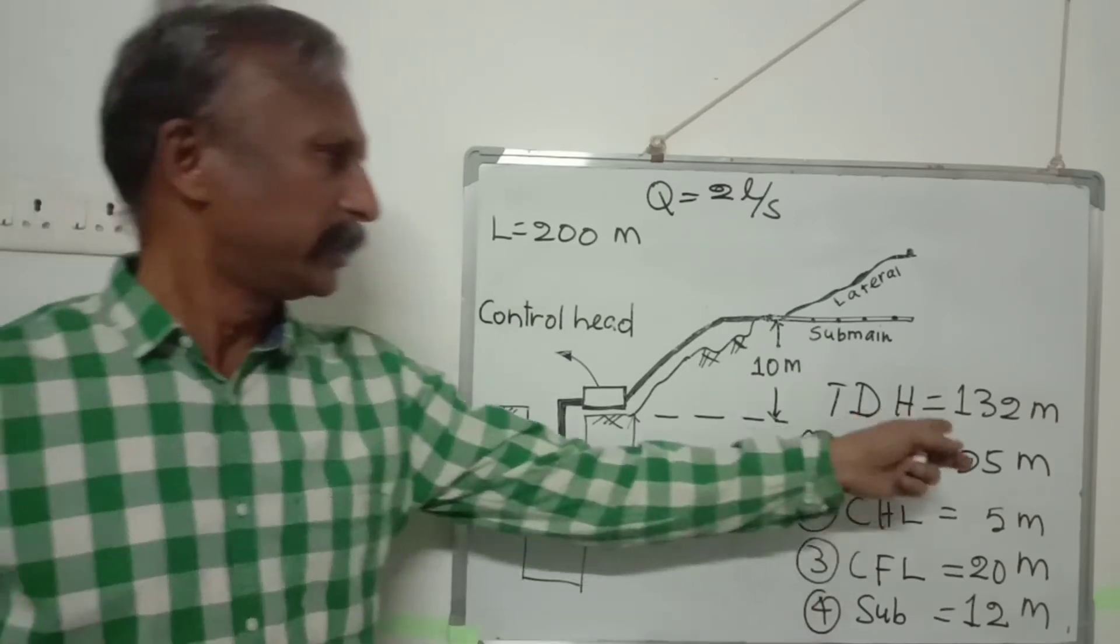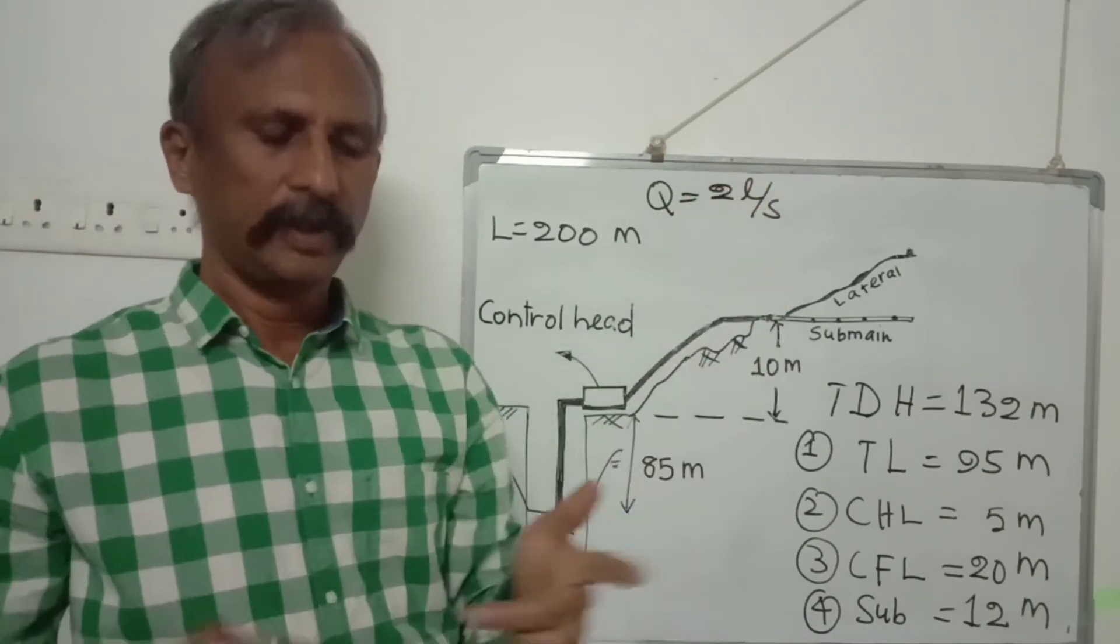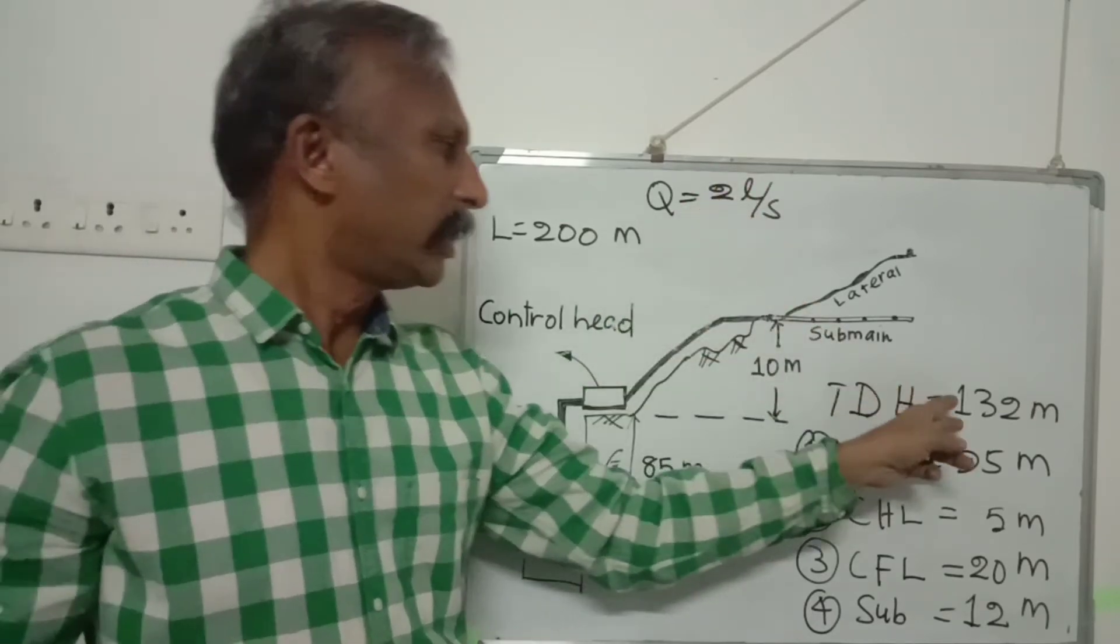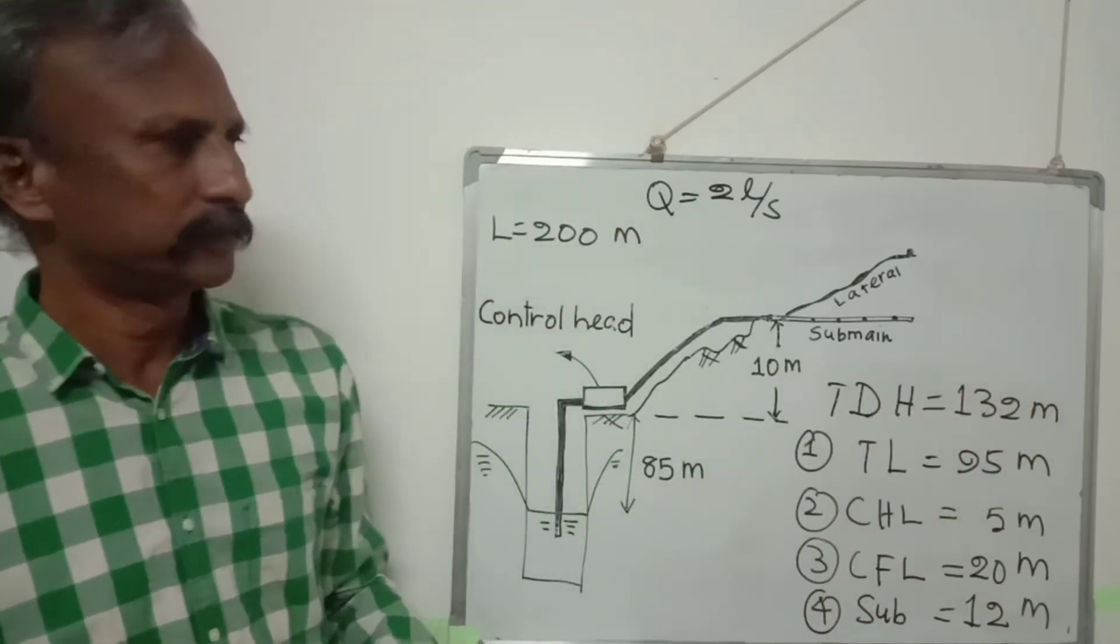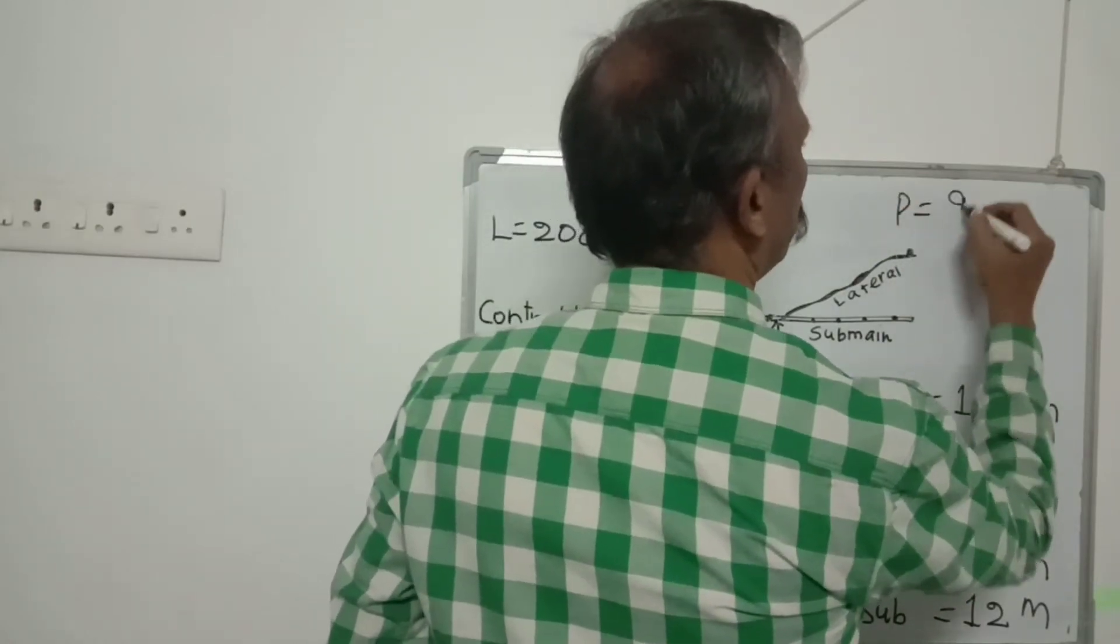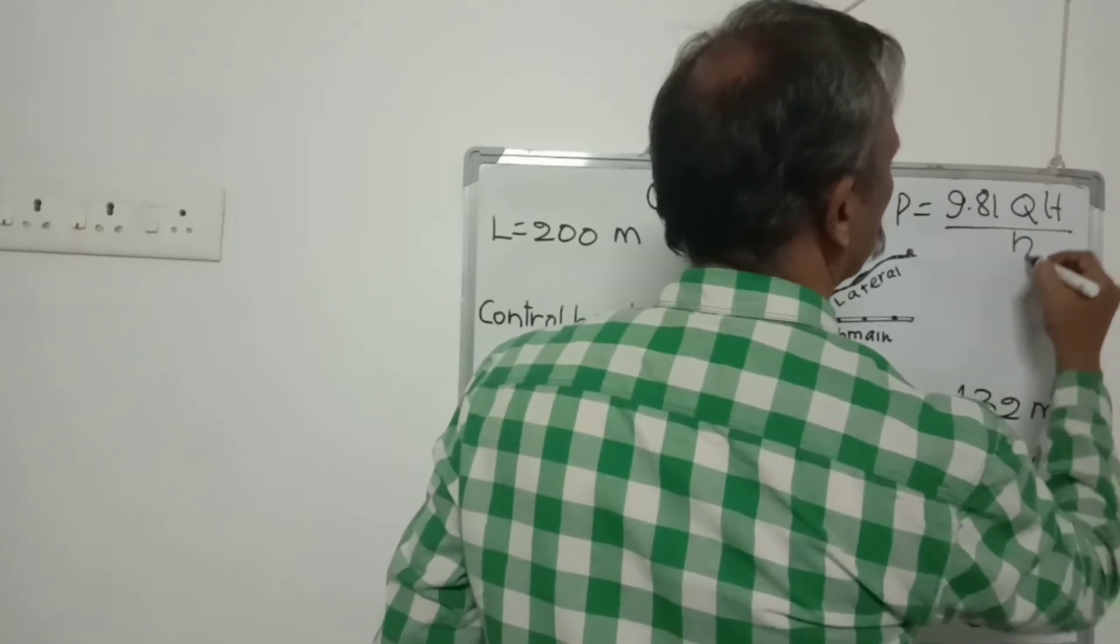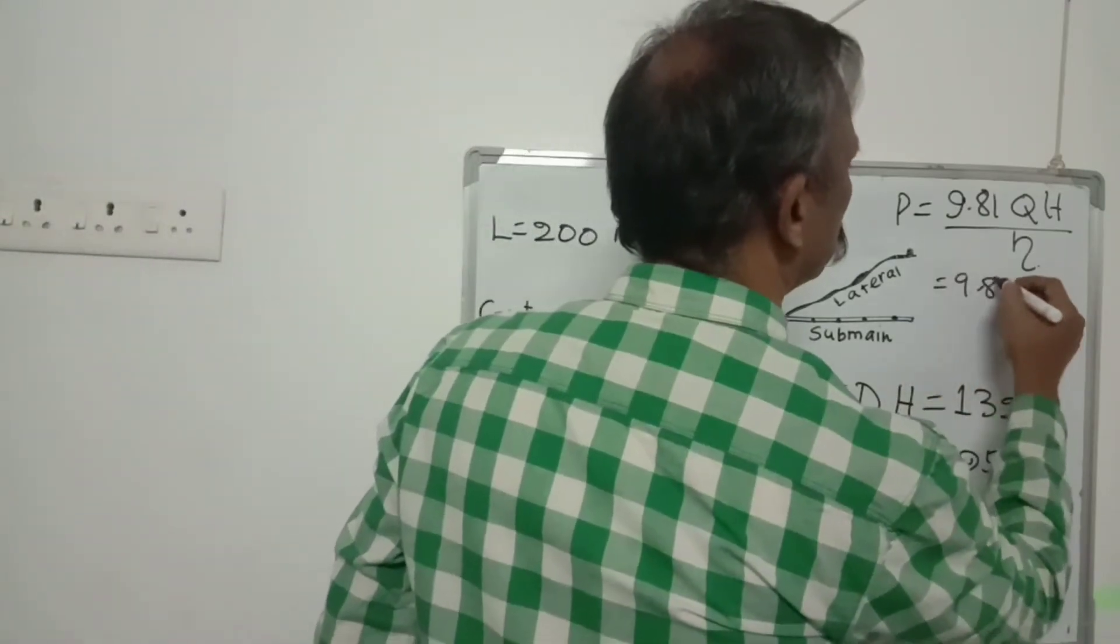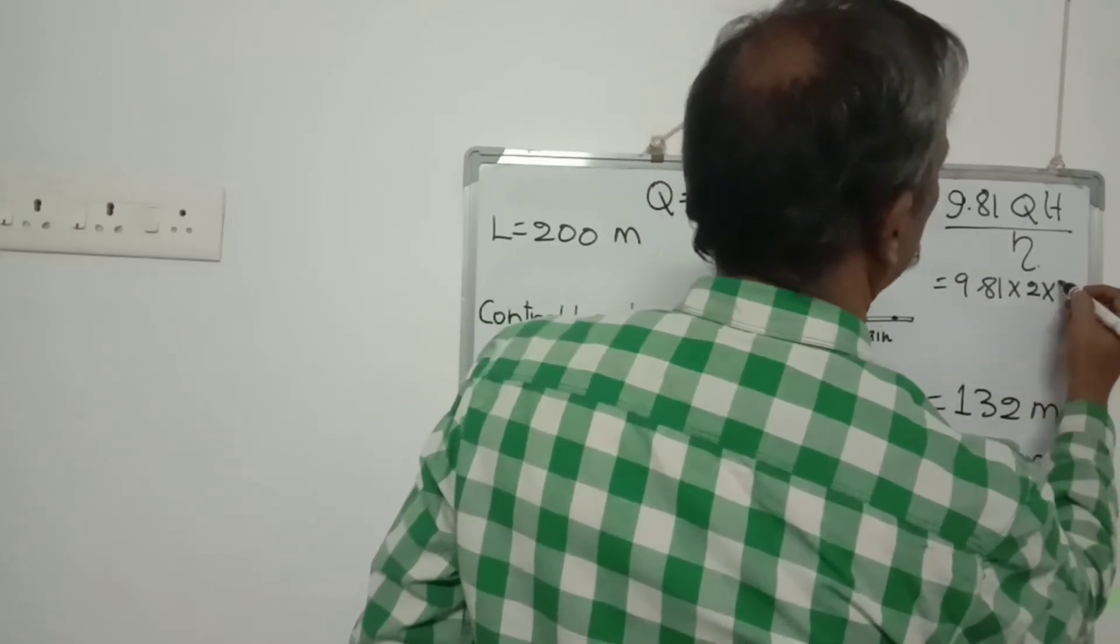Next, using this 132 meters pressure head and 2 liters per second, we need to purchase a pump which can deliver 2 liters per second and can also impart 132 meters of pressure head. For that, the formula is 9.81 × Q × H divided by efficiency. So 9.81 into 2 liters per second and H is 132 meters.